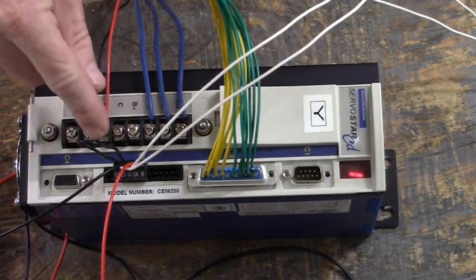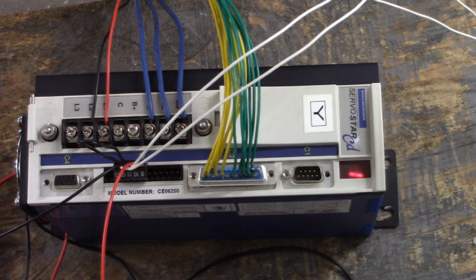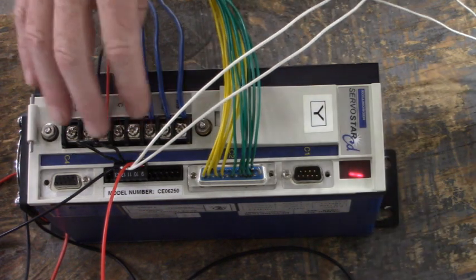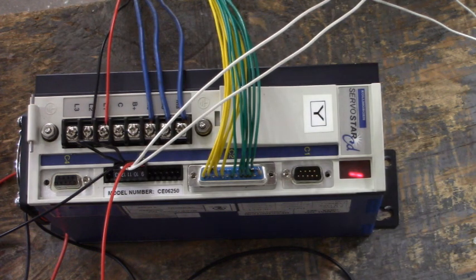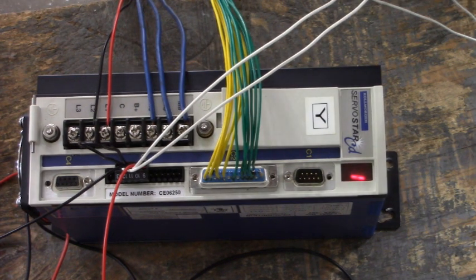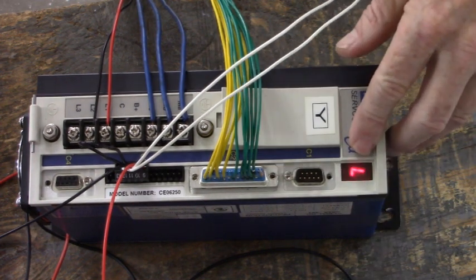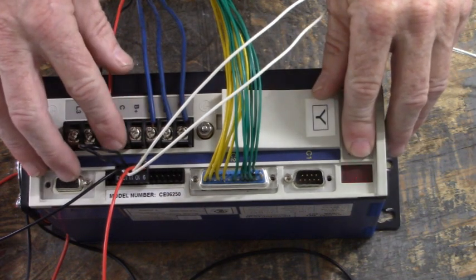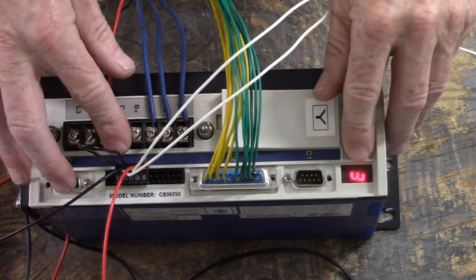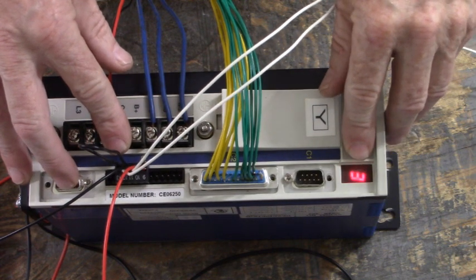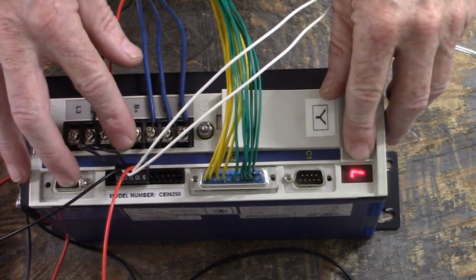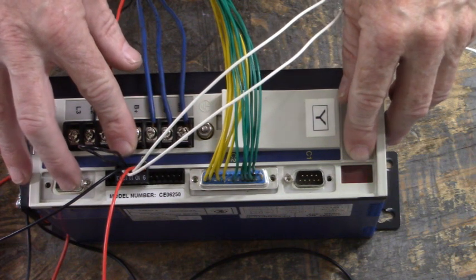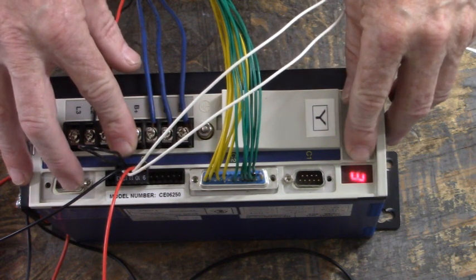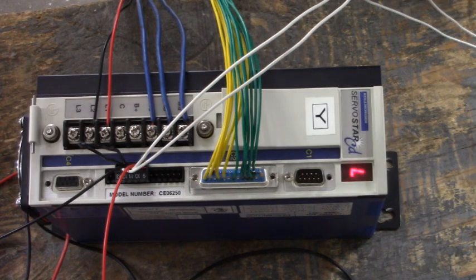Now there's two limits. There's the clockwise limit and the counterclockwise limit. I'm going to remove the 24 volts DC from those inputs. Let me turn that power off. We'll see what we get. There we go. There's L3. That's the limit going into C3 pin 10. If you get L2 in the display, that's the limit going into C3 pin 9. Let's turn that 24 volts back on, and we're back and ready to go.